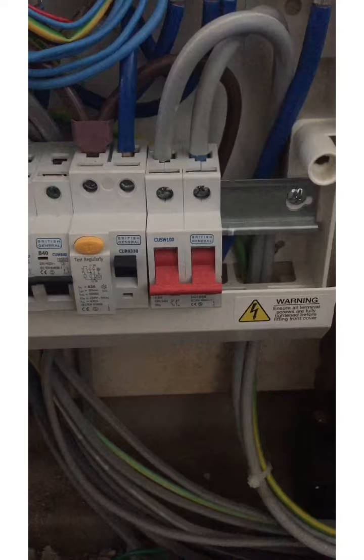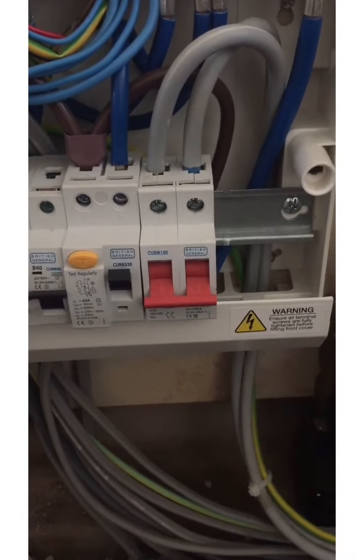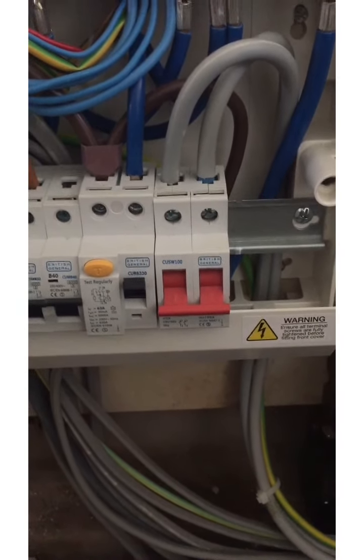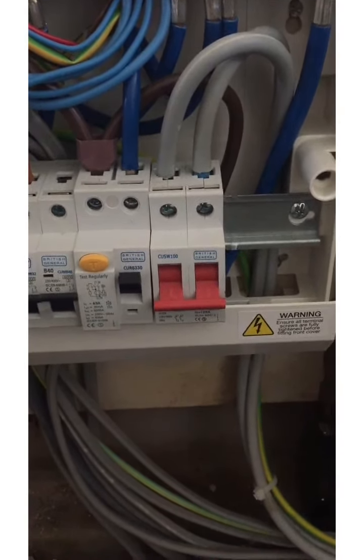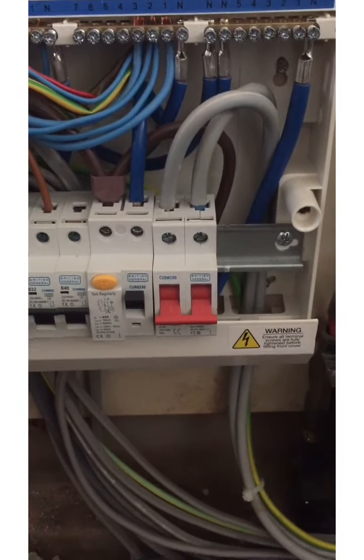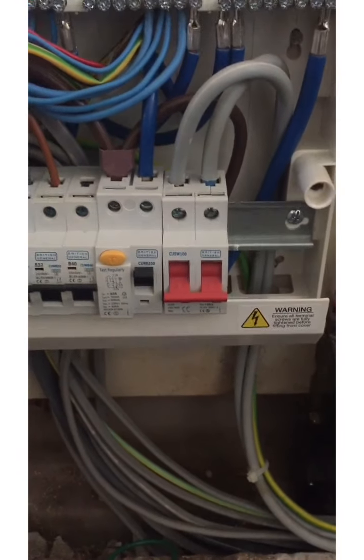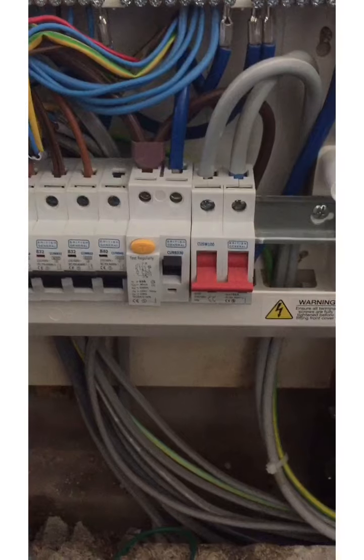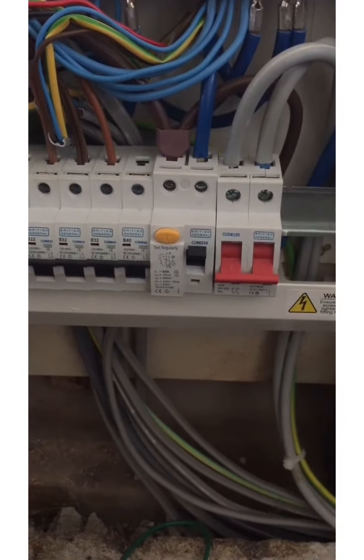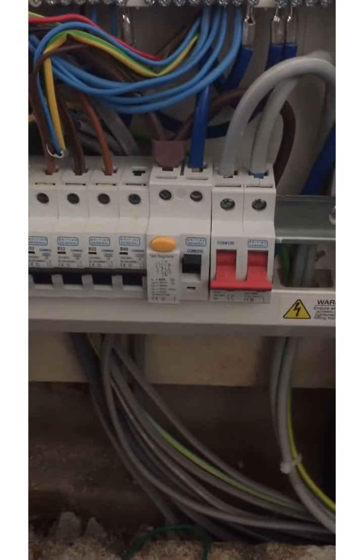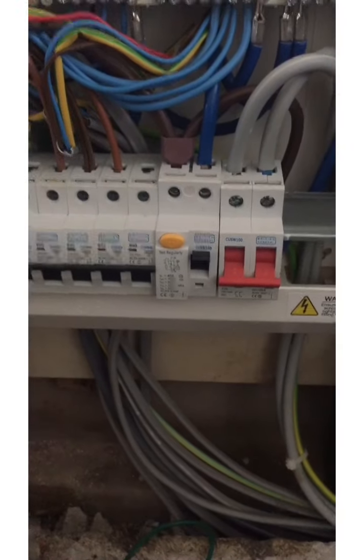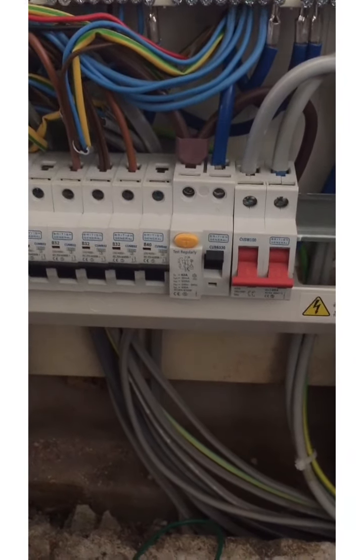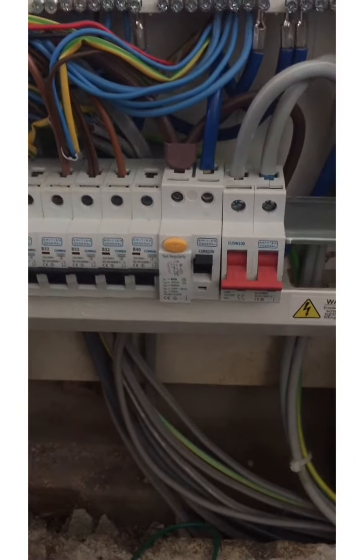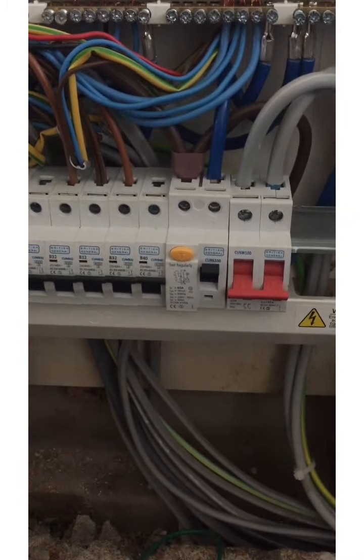As I've mentioned all the time: risk assessment, method statements, notifying people, permits to work, all the rest of it. At the back of our minds, we're always doing a risk assessment. In these circumstances, I'm happy that this board is under my supervision, and that it'll stay under my supervision until I've finished the test and I've got the covers back on, and the test has all been done.